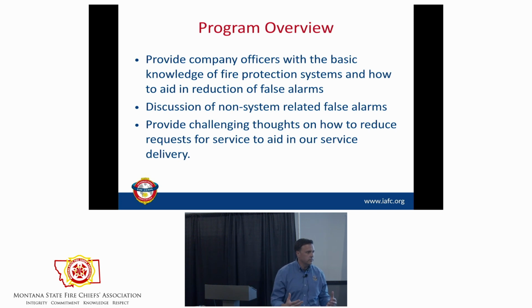How do we know that? Right? Fire alarm systems are very robust. Just like your smoke alarm in your home has a battery backup, every commercial fire system has very detailed backup secondary power. Right? It's supposed to last us 24 hours minimum. Right? And so that very robust should take care of the power flickers. And it had to do with a fire pump. Now, why is it important to know that it had to do with a fire pump connection?